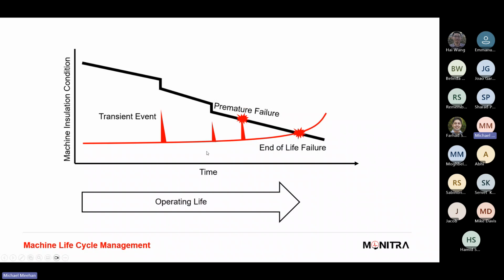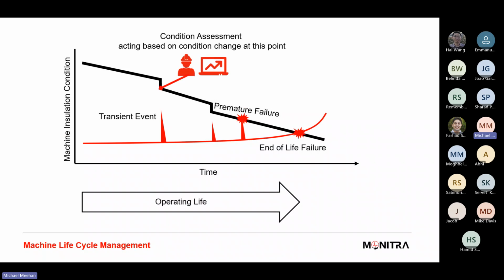So to remove that risk of premature motor failure and extend the end of life, which is the strategy of the asset owners and engineers, we can introduce a condition assessment based program where we start to look at some of those key failure modes. What we really want to do when we do that is identify how we can best track them, report them, trend them, and correlate the information so it's not lost, and we start to piece things together. And when we do that, we can increase that trend line from being more downward facing to more horizontal, extending that end of life and removing the risk of premature failure.